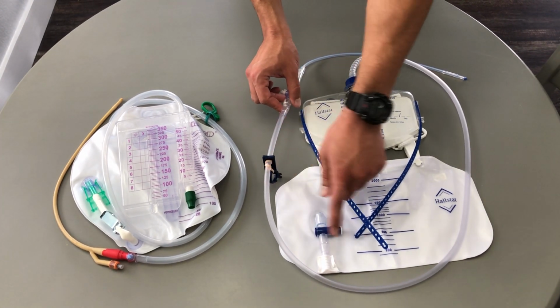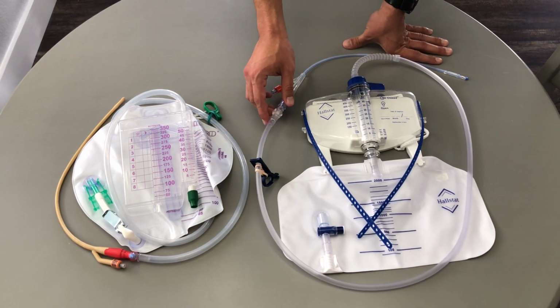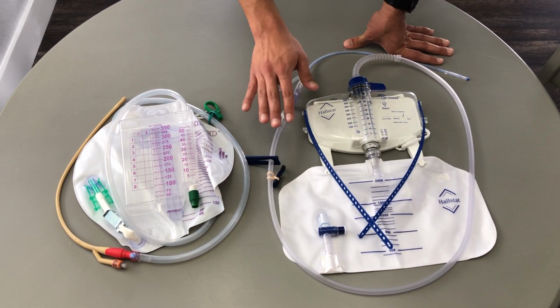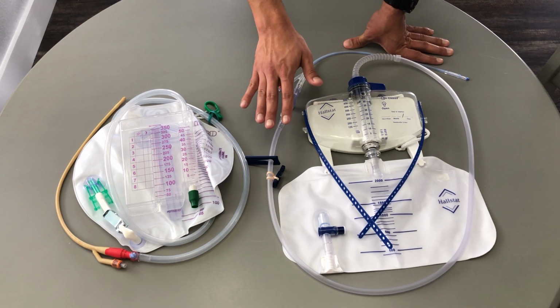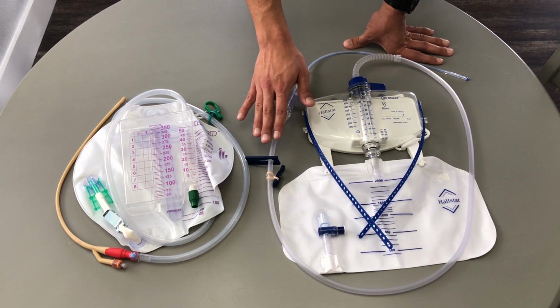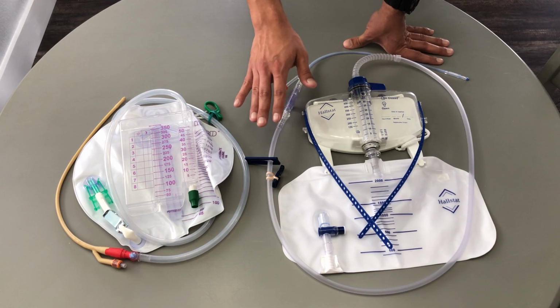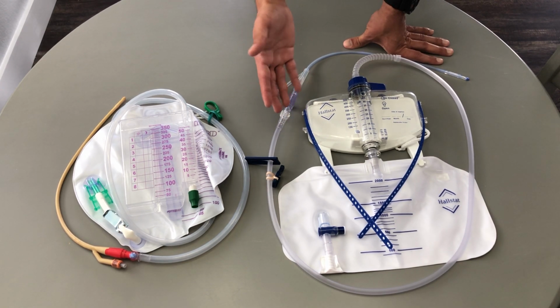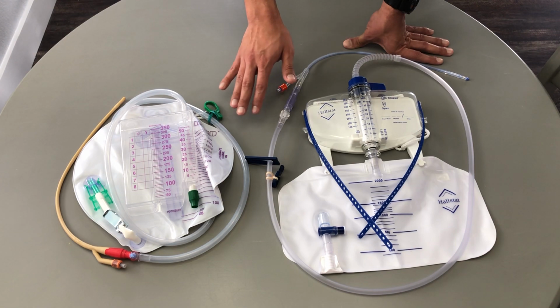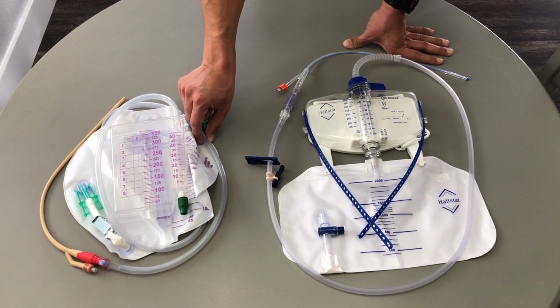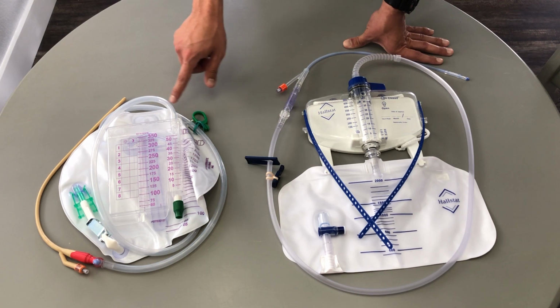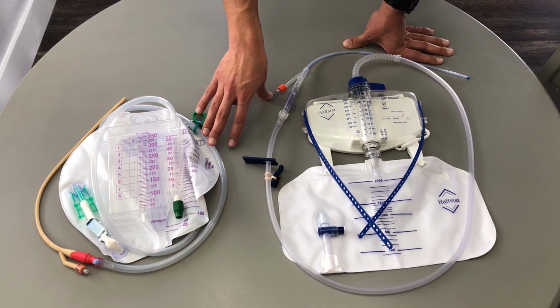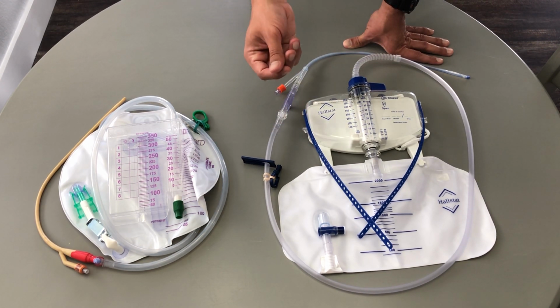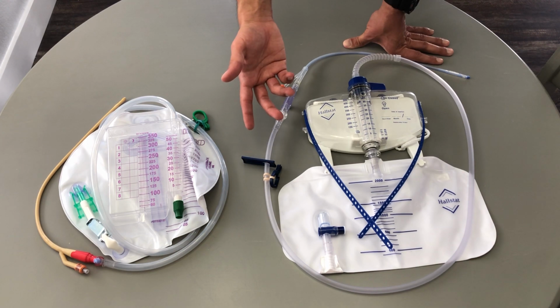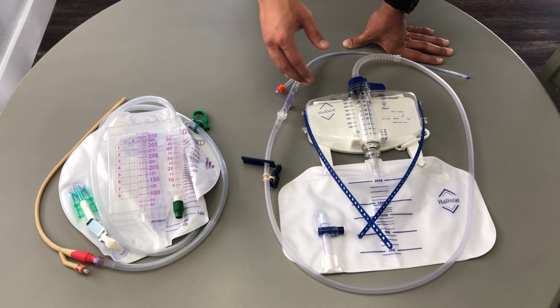Our drainage tubing also has a bacteriostatic coat, so similar to Bard's, but we believe that our technology and what we're infusing inside of our polymer is actually more effective at reducing bacterial growth than Bard's. At the same time, Bard's drainage tubing, they report that with time it elutes, so it loses its strength and its capability to reduce bacterial growth. Whereas in the Hallstat system, it is infused inside the plastic, so it never runs out. It always stays as effective throughout time.